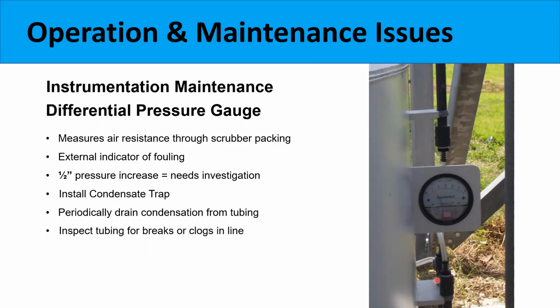of condensate buildup. A lot of times that's one of the issues that we see, that there's no condensate trap installed on that magnehelic gauge, and just enough condensate will clog that pressure reading and cause that magnehelic gauge to read erroneously. So it's good to have condensate traps with little drain valves on them that you periodically go and check to keep the condensate out of it.